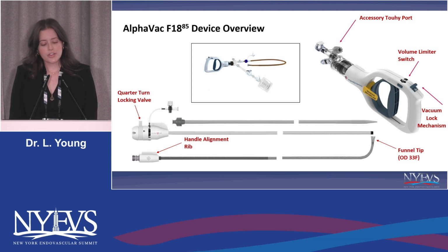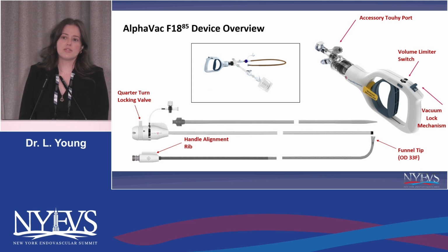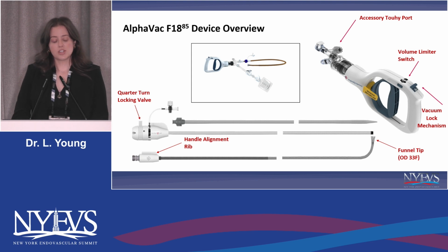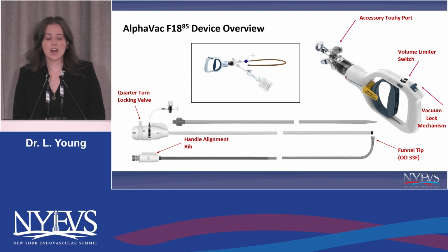There's a handle alignment rib on the back of the catheter, which allows you more torqueability to navigate it around in the pulmonary arteries and gives you an orientation of where the curvature of the catheter is. There's a quarter turn locking valve on the sheath, which essentially allows you to lock that orientation of the cannula within the sheath if you don't want it to move around.